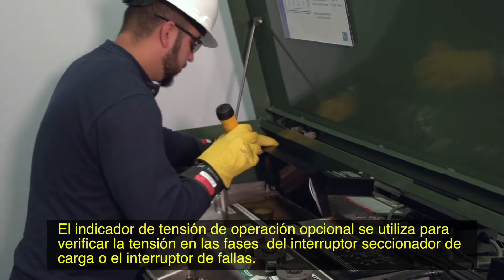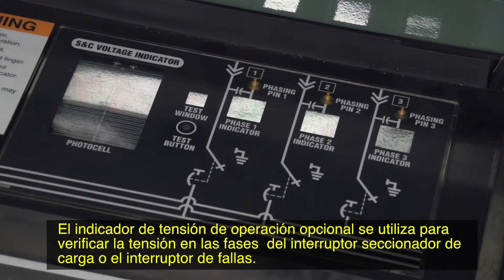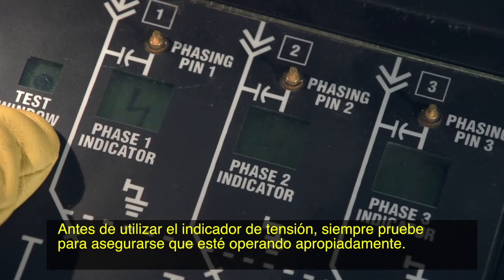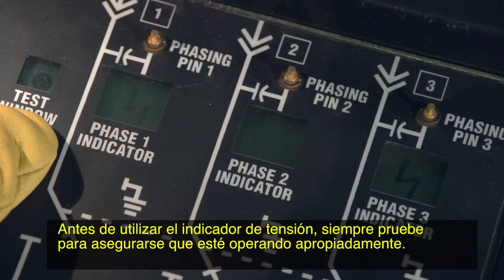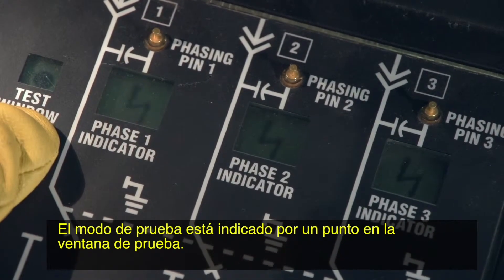The optional voltage indicator is used to check for voltage on the phases of the load interrupter switch or fault interrupter. Before using the voltage indicator, always test to make sure it is operating properly. Clean the surface of the photocell and the test button if necessary. If the photocell is dirty, the voltage indicator will be in test mode and may give a false indication that all three phases are energized. The test mode is indicated by a dot in the test window.